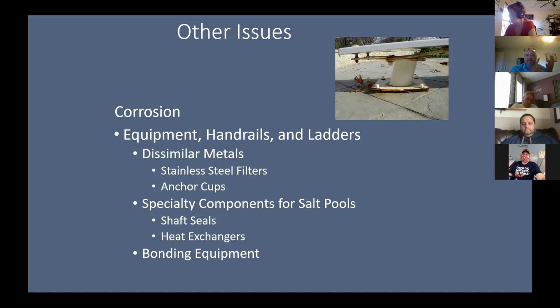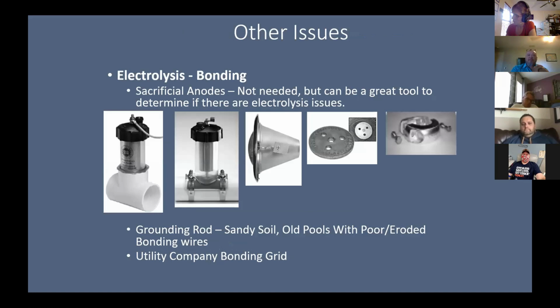metallic: handrails, light rings, ladders, stainless steel anchors. So it's looking to attack those things. When it's properly bonded, it discharges safely by way of that electrical bond, okay? So sacrificial anodes are offered to the industry as a way of trying to protect against salt damage. Now, when we look at a bonding issue, if there's a bonding issue, the bonding issue's got to be corrected, okay? A sacrificial anode is not the correction for a poorly bonded pool.